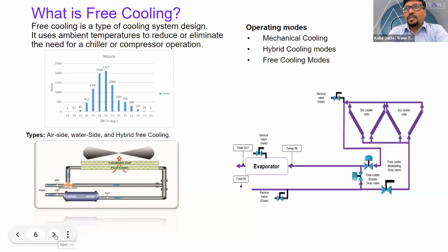But what happens in a hybrid cooling solution, which is very important for most of the climatic conditions of our country, because we don't live in a very cold climate like most of the European countries and some parts of North America, where there is a lot of flexibility in the ambient condition to operate these free cooling chillers. Hybrid cooling is very much applicable in our case, and all modern chillers incorporate mechanical cooling sandwiched with free cooling circuits, where you can encash the benefit of hybrid cooling advantages.